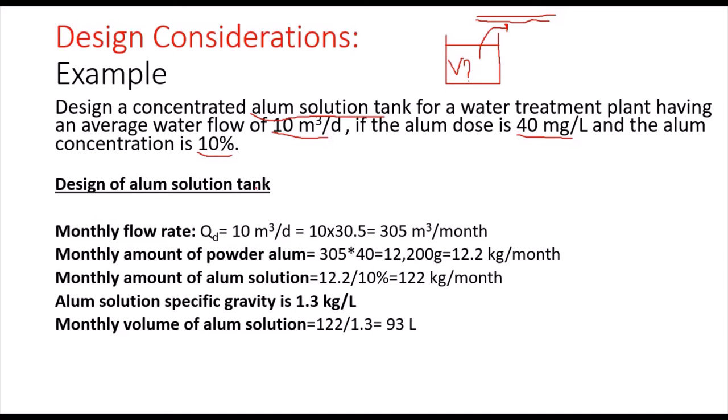Now first of all, we will fill this solution tank once a month. You can choose to fill it once a week, but in this example, we will be filling this solution tank every month. So that's why we will have to convert the 10 cubic meters per day into months. We will multiply it by the average days per month, which is 30.5. So 10 times 30.5 will be 305 cubic meters per month.